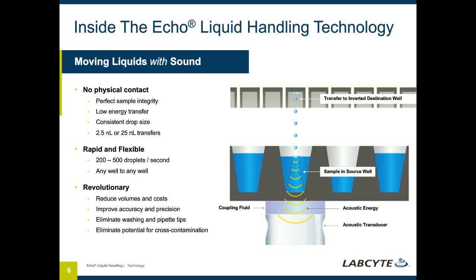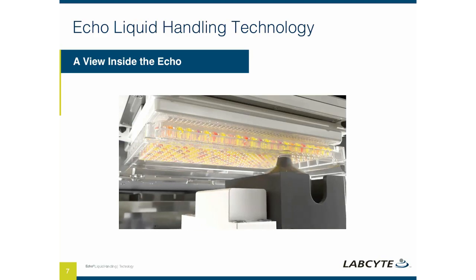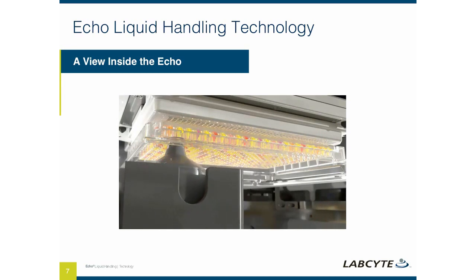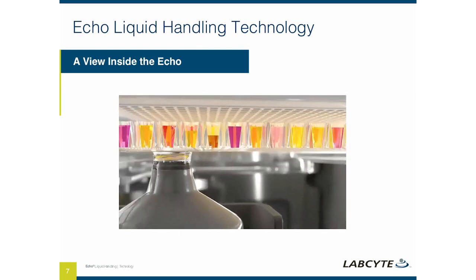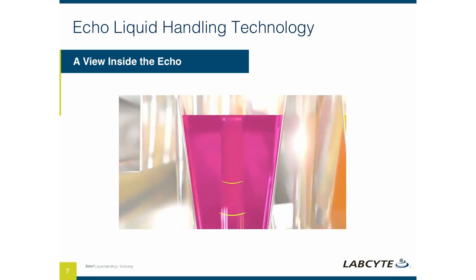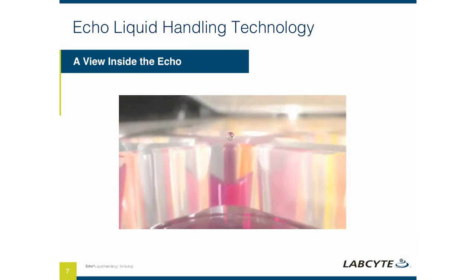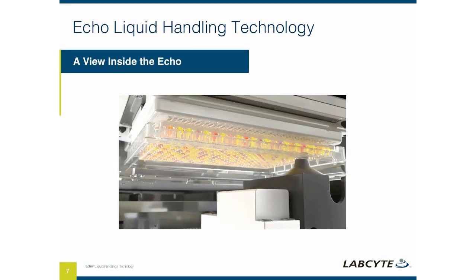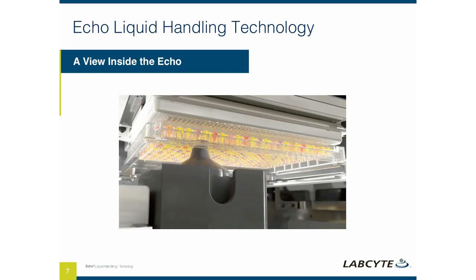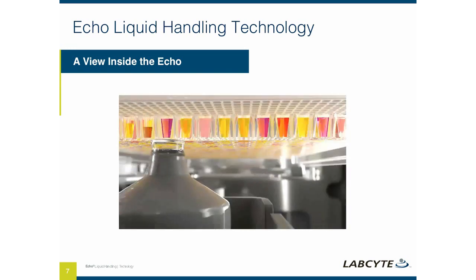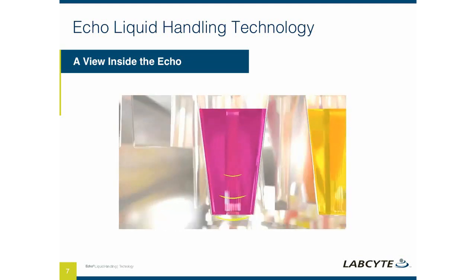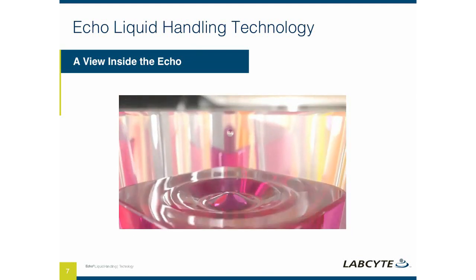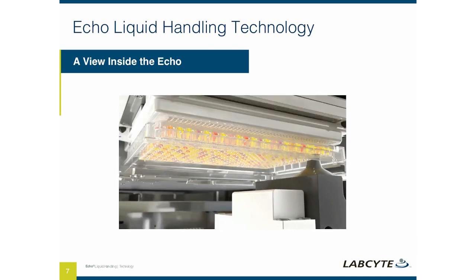So hopefully, in the next slide here, we'll be able to provide video. There we go. So this is the instrument in action. What you see is the transducer moving across the bottom of the plate. It's going to dwell under a particular well. Now it's emitting that sound energy. That sound energy is focused on the surface of the fluid there, and it's ejecting a droplet out of that. We can position that transducer under any of those wells, and then that droplet is traveling to a plate. You can see it in this particular view right here that's positioned above it.